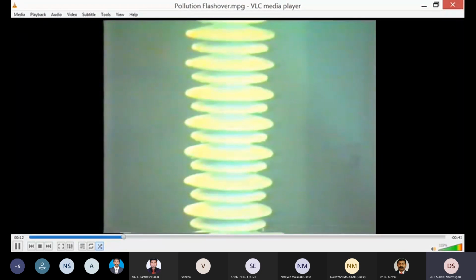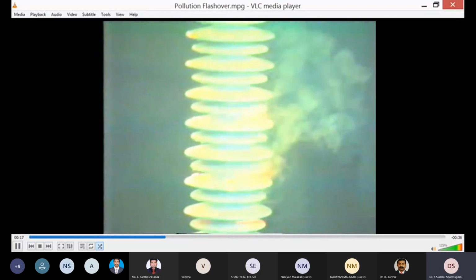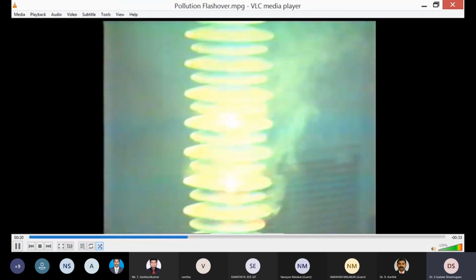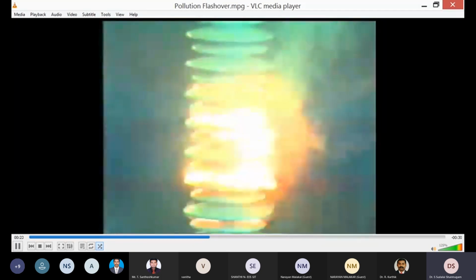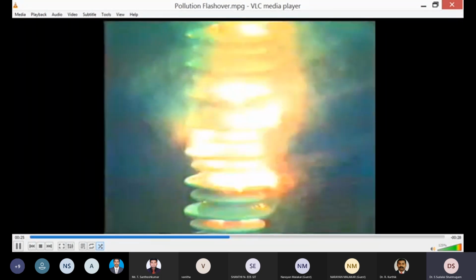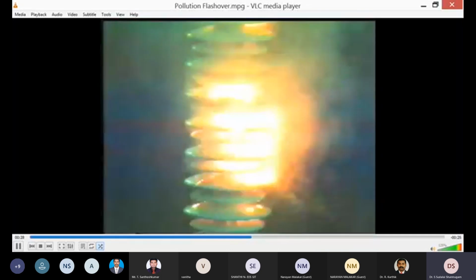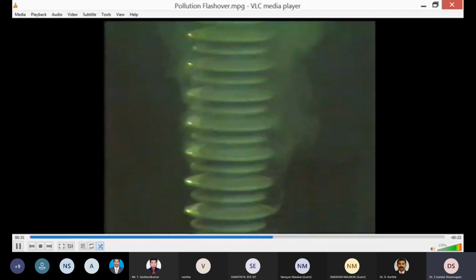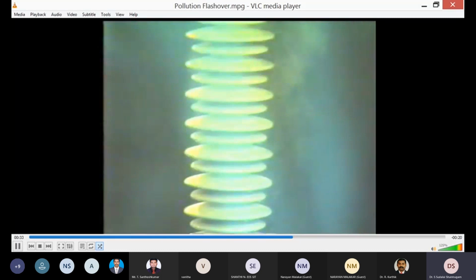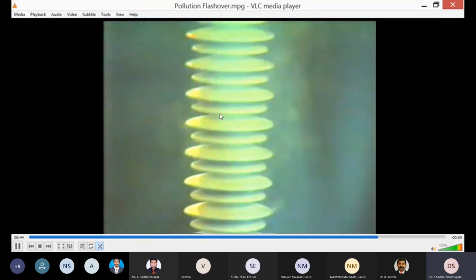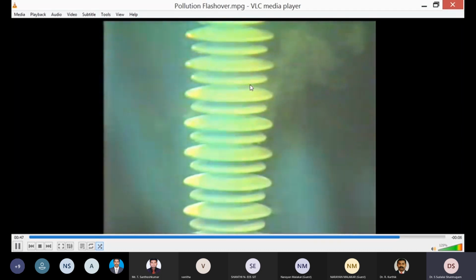Let me explain now. What you are seeing is an insulator coated with contaminant. We are applying voltage on that. What you are visualizing is known as scintillation. Scintillation is nothing but minute arcs trying to bridge each other. Scintillation progresses to flashover, and if the scintillation progresses to two-thirds of the length of the insulation, then it will result in flashover. What you are seeing right now is known as the solid layer test, which is conducted in the laboratory. This is replicating industrial pollution occurring on the high voltage lines of India.